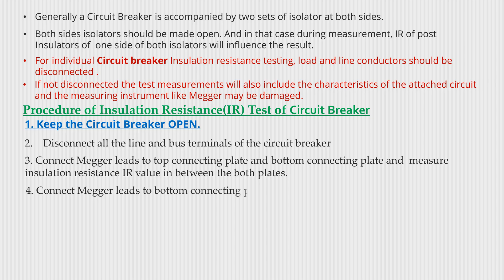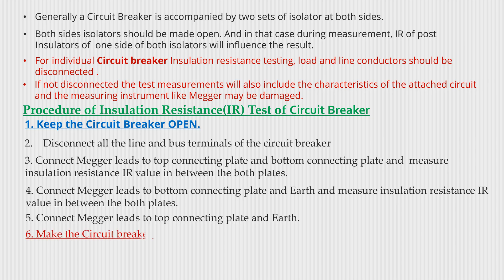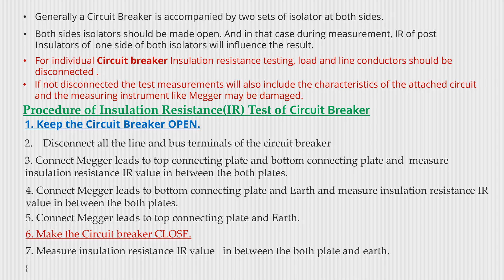Connect the megger leads to the top connecting plate and earth. Make the circuit breaker close. Measure the insulation resistance IR value in between both plates and earth. Note down the reading in the given proforma.